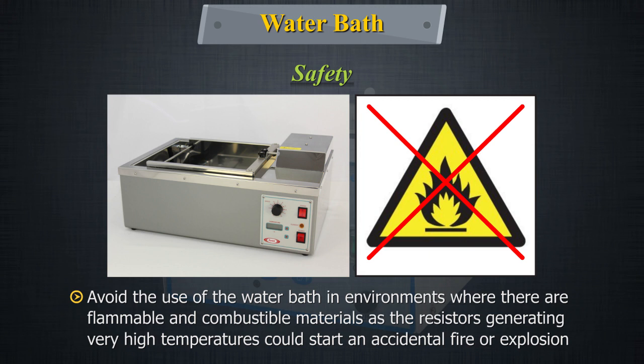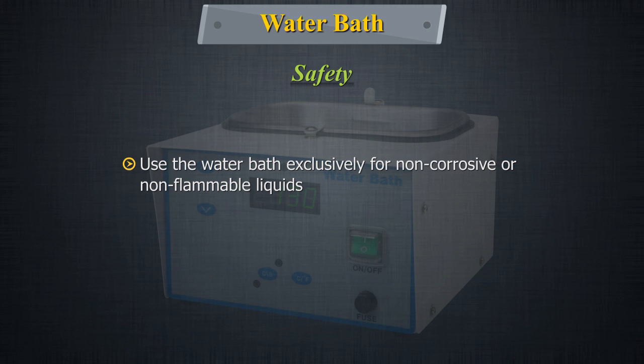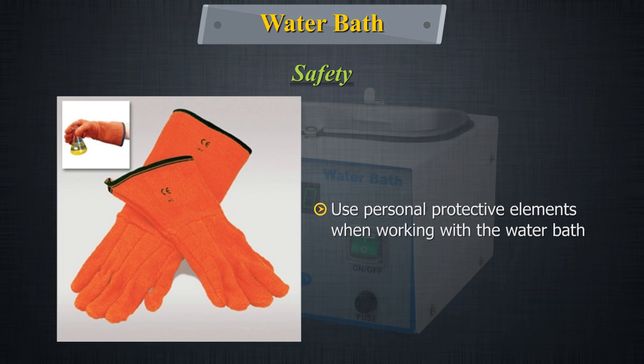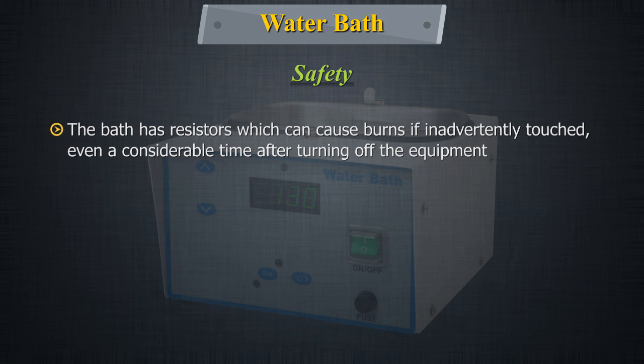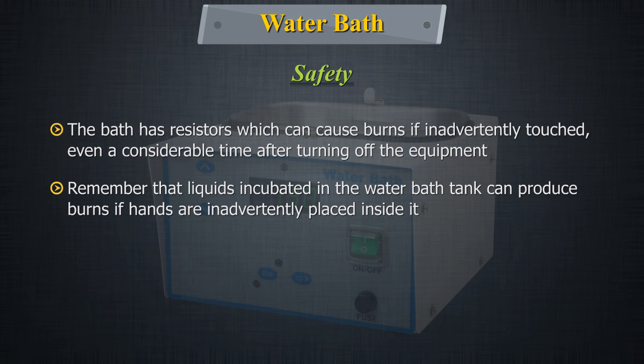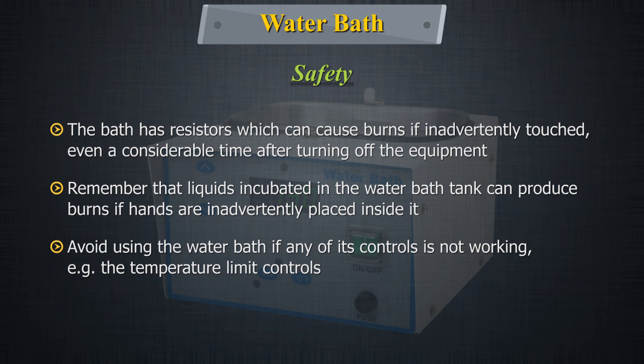For safety, avoid the use of the water bath in environments where there are flammable and combustible materials, as the resistors generating very high temperatures could start an accidental fire or explosion. Use the water bath exclusively for non-corrosive or non-flammable liquids. Use personal protective equipment when working with the water bath. The bath has resistors which can cause burns if inadvertently touched even a considerable time after turning off the equipment. Remember that liquids incubated in the water bath can also cause burns. Avoid using the water bath if any of its controls, such as the temperature or limit controls, are not working.